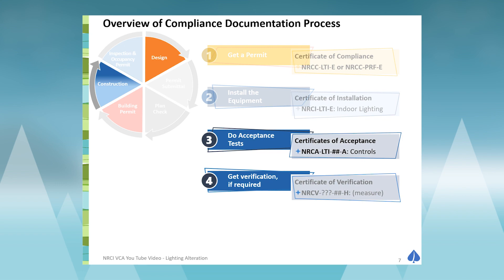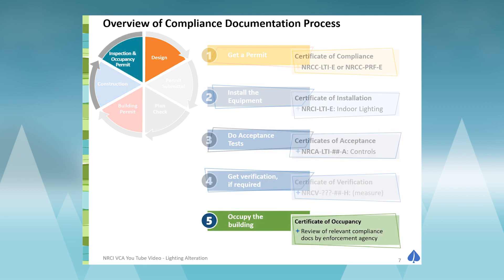The Certificate of Acceptance Forms are produced by the Certified Acceptance Test Technician, who does functional testing of the lighting controls as dictated by the Energy Code. Only a Certified Acceptance Test Technician can provide those forms for indoor lighting projects. Certificate of Verification Forms are for HERS measures, and there are no HERS measures for lighting alteration projects.